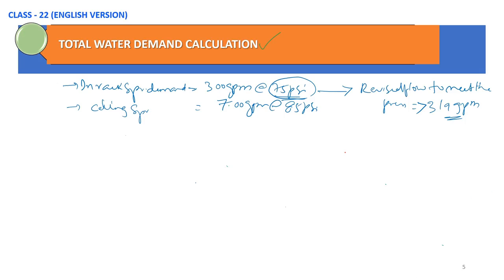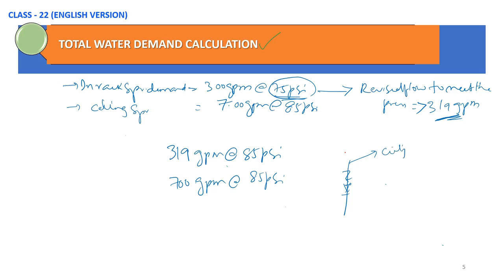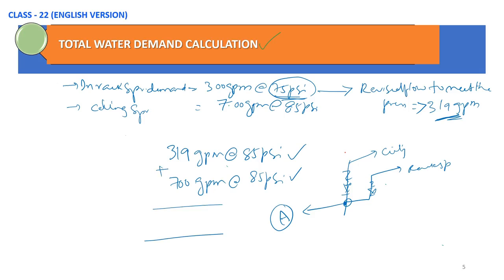We now have the revised in-rack sprinkler demand as 319 GPM at 85 PSI, and the ceiling sprinkler demand as 700 GPM at 85 PSI. Since both are now at the same pressure at connection point A, we can add them: 319 plus 700 gives approximately 1019 GPM. This is the total water demand for this particular warehouse.